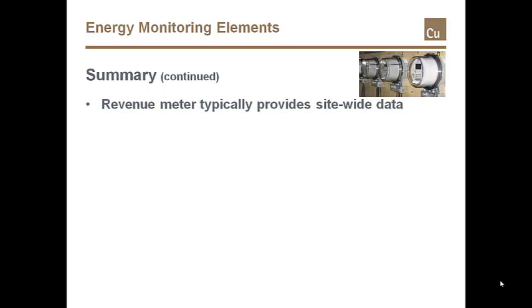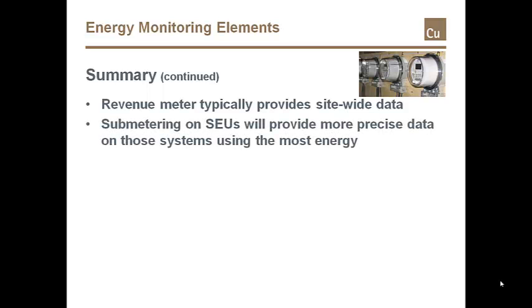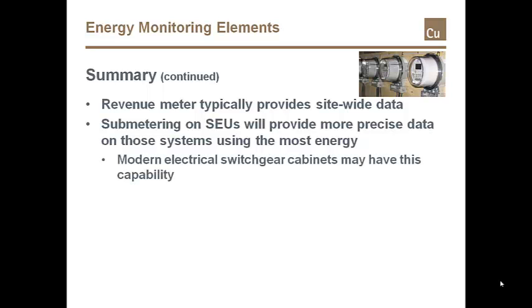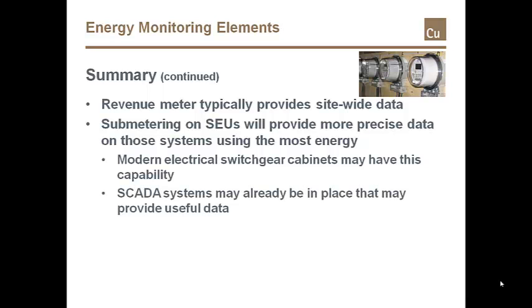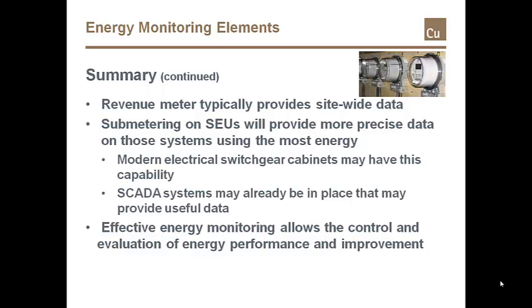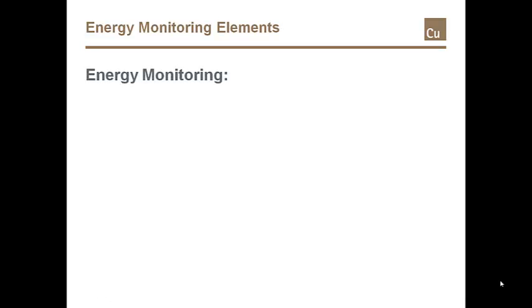The revenue meter typically provides site-wide data only, although some sites may have multiple revenue meters. Sub-metering on SEUs will provide more precise data on those systems using the most energy. Modern electrical switchgear cabinets may have this capability already built in. SCADA systems may already be in place that provide useful data on energy use as well as other parameters. In conclusion, effective energy monitoring allows the control and evaluation of energy performance and improvement. Energy monitoring. Seeing is believing.